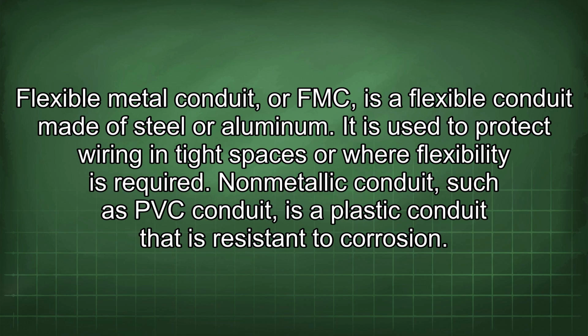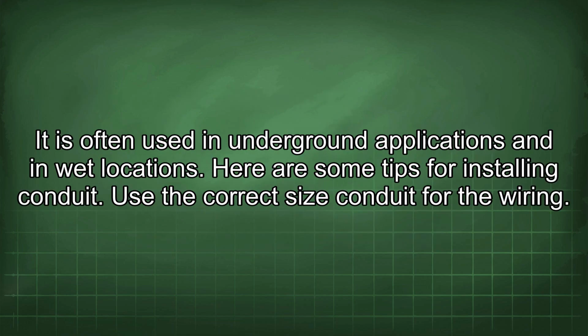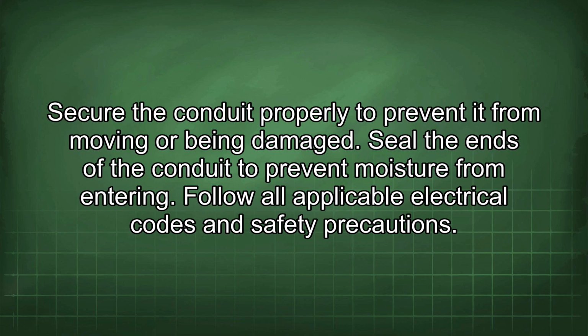Non-metallic conduit, such as PVC conduit, is a plastic conduit that is resistant to corrosion. It is often used in underground applications and in wet locations. Here are some tips for installing conduit. Use the correct size conduit for the wiring. Secure the conduit properly to prevent it from moving or being damaged. Seal the ends of the conduit to prevent moisture from entering. Follow all applicable electrical codes and safety precautions.